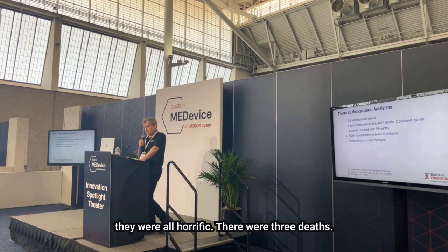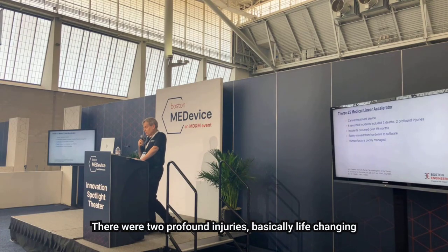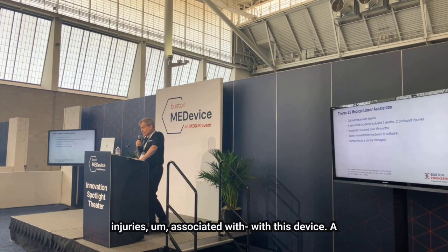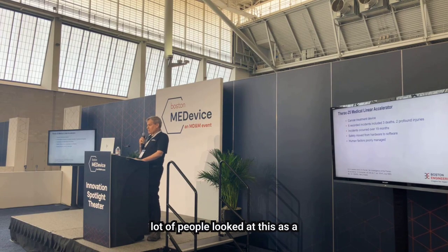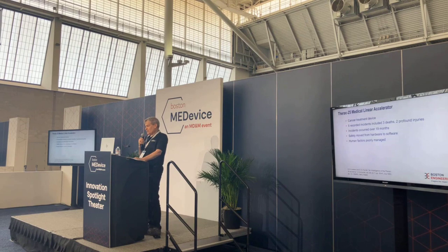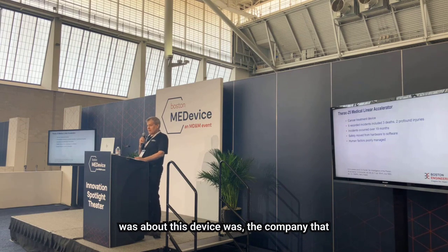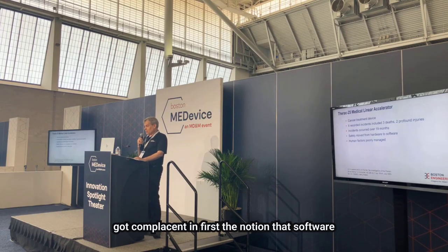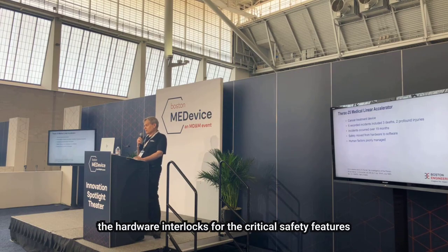They were all horrific. There were 3 deaths. There were 2 profound injuries, basically life-changing injuries associated with this device. A lot of people look at this as a case study in how to do poor software development. But what it was about this device was a company that got complacent in first the notion that software can cure all ills, and they took out the hardware interlocks for the critical safety features of this device.